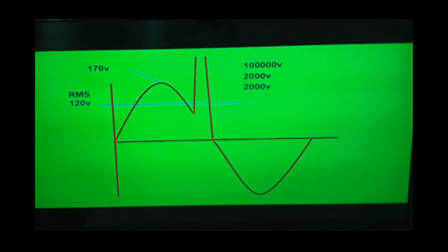But now the problem here is you get what are called transient voltages. You get lightning strikes, let's say within six blocks from you, half a mile away. It doesn't have to hit a power line, all it has to do is hit close by. You could very easily have a transient going through the electrical system in your building in excess of 100,000 volts. Well, if you're taking a reading with a meter that's only rated for 1,000 volts or 600 volts, that meter explodes.